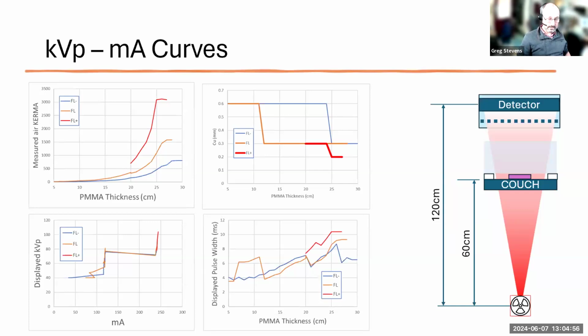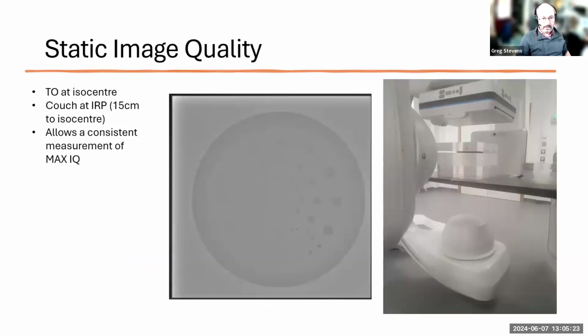The other thing, of course, is that under the old systems your copper filtration would be a function of the fluoro flavour if it was Philips, essentially your low, medium and high dose buttons. That's no longer true. Copper filtration happens about halfway through the medium, the normal range, and then drops quite rapidly after that. Now, when I complained about the recursive filter in there, you can still measure image quality, but this is kind of the maximum image quality possible on the system.